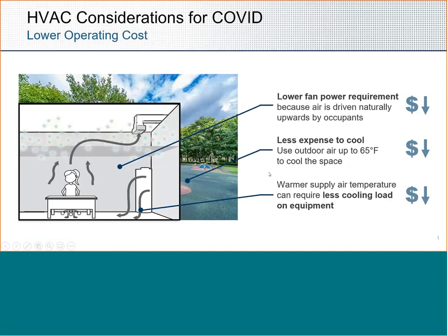There are other opportunities. As I hinted at earlier, because this is a naturally buoyancy-driven system, you're not really pushing at high static. The underfloor air system is really served by 0.05 inches of static underneath the floor plate, really helping reduce the fan power requirement for the building. There's also less expense to cool if you're able to utilize free cooling, 100% outside air up to 65 degrees, especially in some climates. In a lot of cases, that can be a huge benefit.